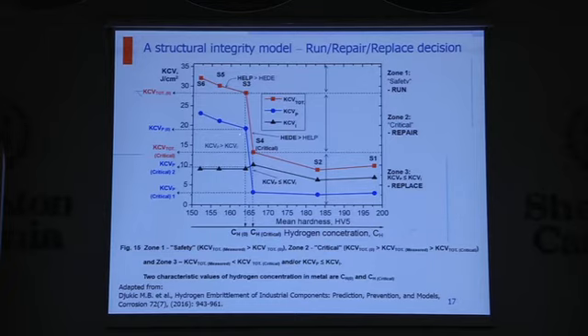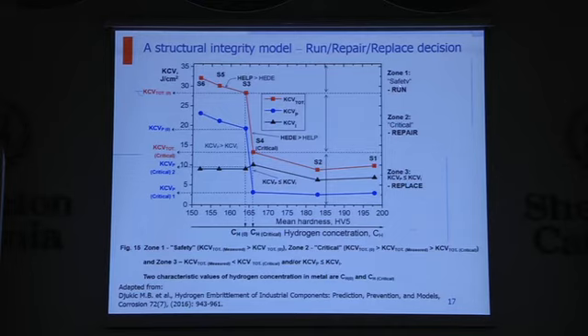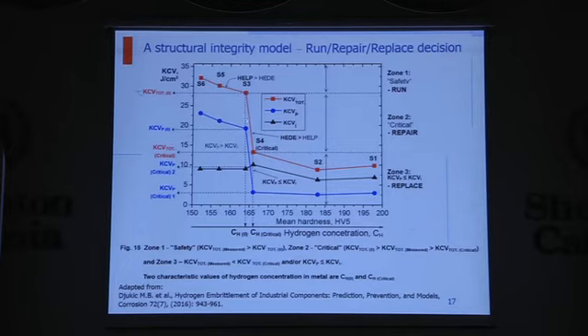The idea is: you can investigate specimens from an industrial hydrogen-affected component, make the same diagram — we have a reference diagram like this — and provide experimental results. If the new specimen falls in zone 1, that means a decision from the standpoint of preventive maintenance — the component continues in service. If it falls in the critical zone, we should prepare for maintenance. There are two criteria: the first is a critical drop of crack propagation energy; the most important criterion is when the crack propagation energy component is lower than the initiation energy — KCVP is smaller — which is an alert that you are in a critical area.